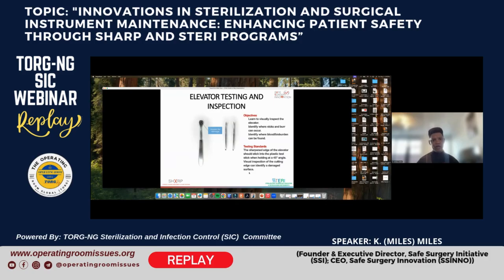Now we have an elevator. Elevators are normally used in orthopedic surgeries, and so elevators normally come with what we call a soft edge. That soft edge is slightly sharp, but it's not like a razor edge like an osteotome. So you want to do a visual inspection from top to bottom, preferably primarily focusing on the distal end. That space is going to come in contact with the patient, so always make sure that there's no nicks, burrs, or damage to this area. If you see that, then you need to remove it out of service and replace it with a different instrument.